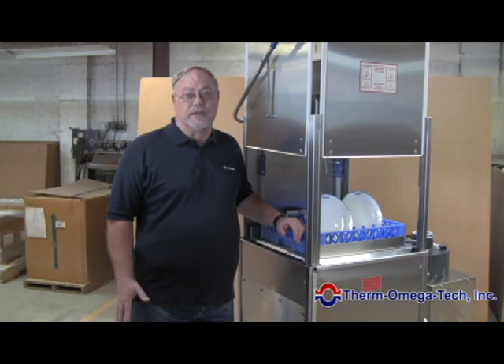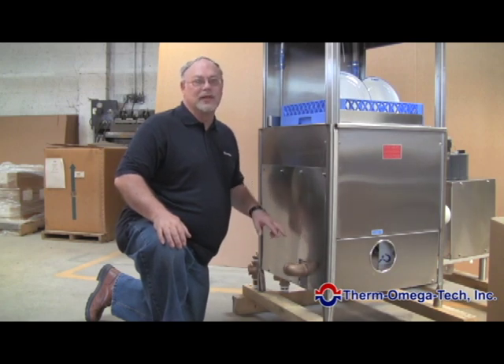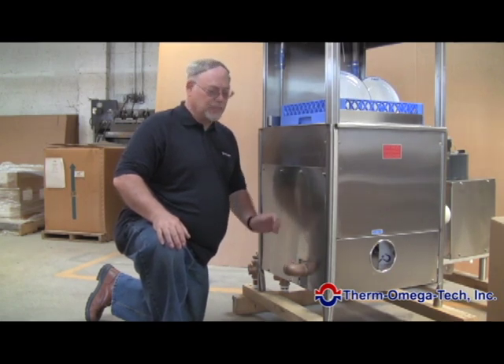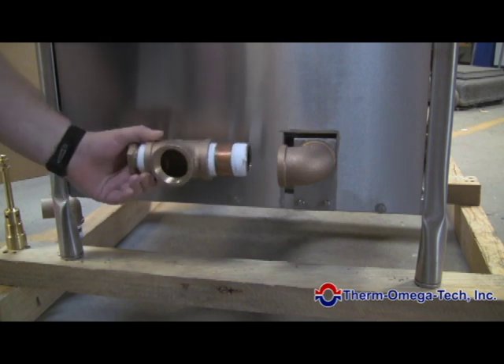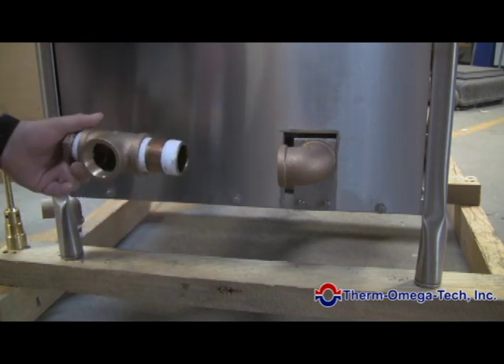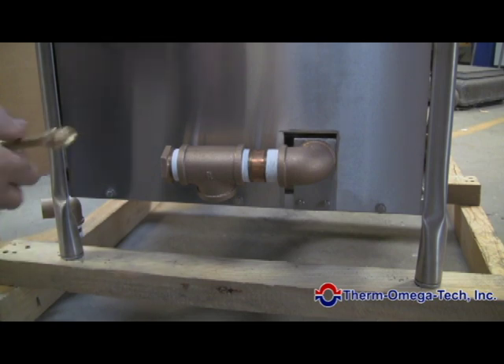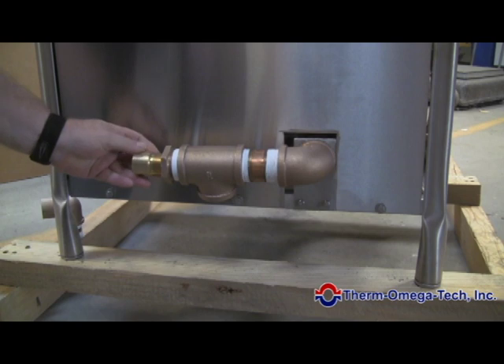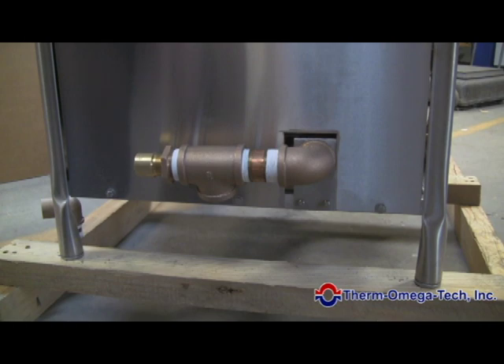In order to cool that down and solve that problem, we install the drain tempering valve — and we'll show you in just a few seconds how easy that is to install. We're going to install the Therm-Omega-Tech drain tempering valve on our commercial dishwasher. This is the standard drain system that would come with it. We add a grouping of fittings — a T fitting and an adapter — and the drain tempering valve is screwed in and inserted into the back of the fittings. We then install a cold water line into the valve, and the drain output is now below the 140 degree requirement for most states.